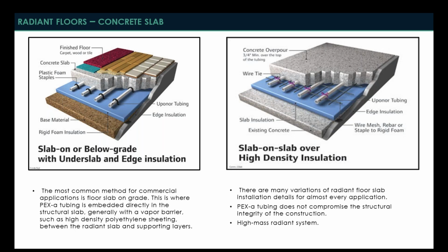You'll notice in both of these images that it's showing a layer of insulation below the PEX tubing. And this is extremely important because energy is going to want to radiate in every direction. And so by putting the insulation in, you're helping direct the energy that's being transferred from the PEX tubing into the slab upwards and into the space where it can actually exchange with the occupants in the space.